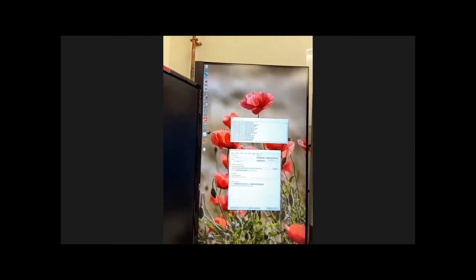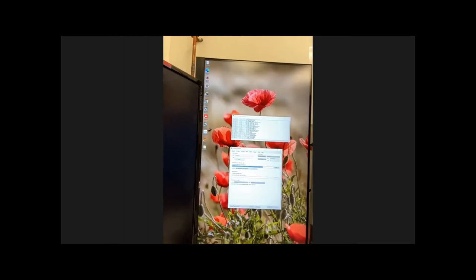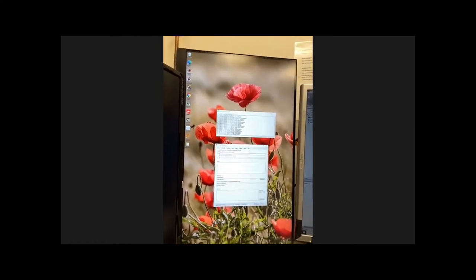And this then allows us to choose which channels you would want to record from, which you choose with something called an IMRO file, which defines which channels you can record from. With the NeuroPixel probes, there are three banks of channels of 384 channels that you can choose to record from. And you can then view your data, hopefully. So here the probe, there's a bunch of noise. The probe isn't in the brain or anything like that. It looks like a few sites aren't great.